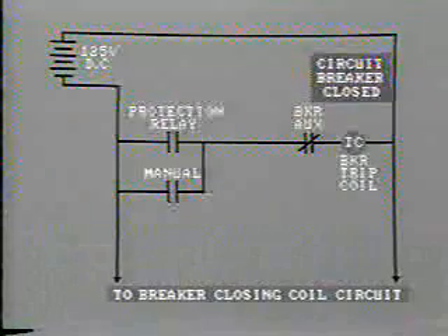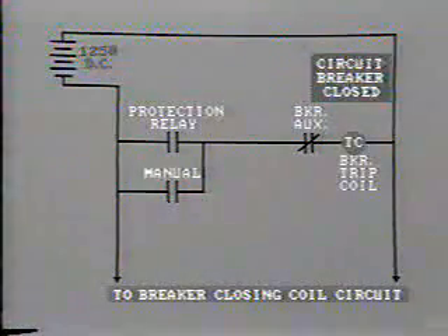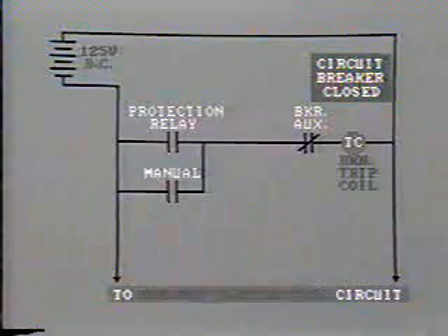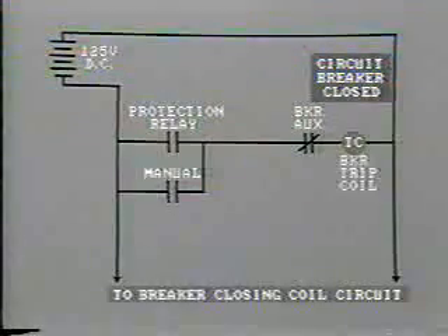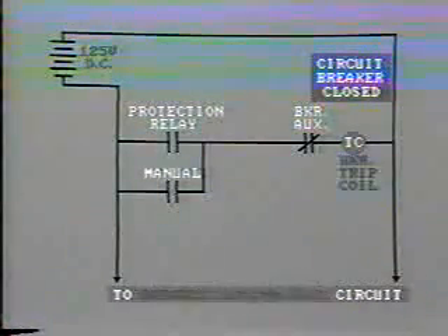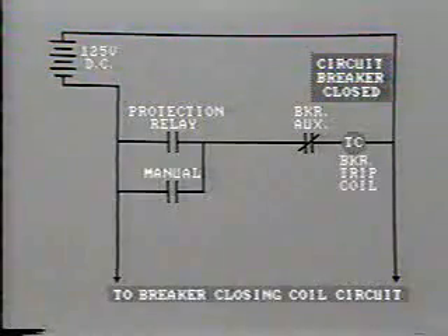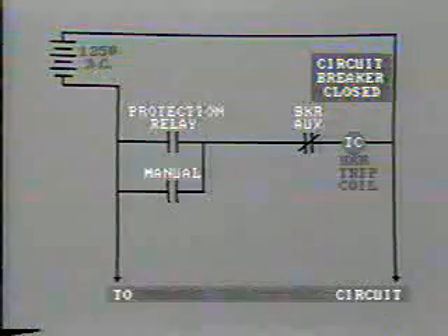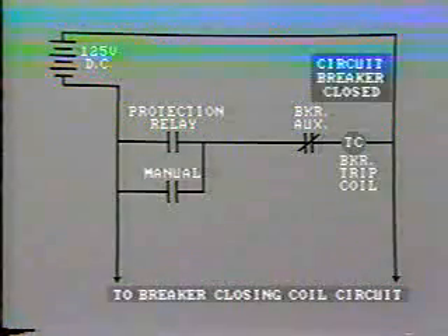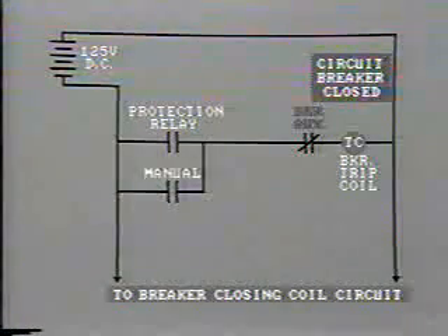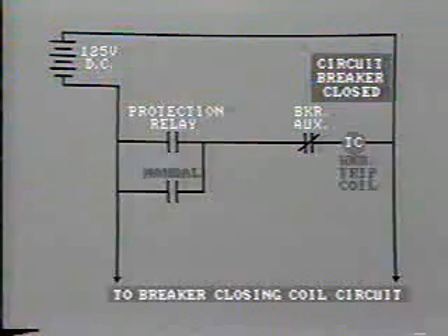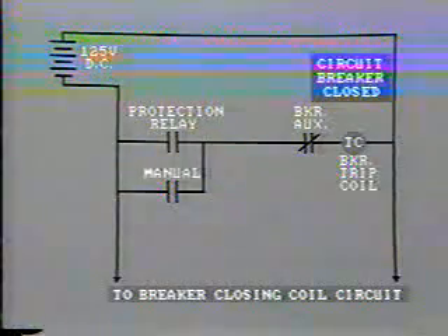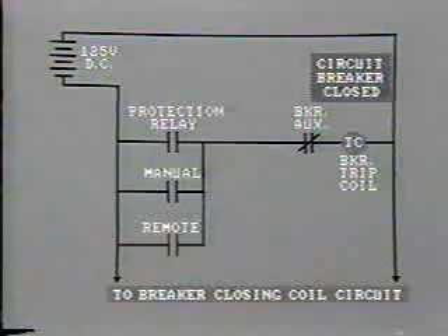Let's look at this tripping circuit. A 125 volt DC system is provided for operation of the breakers. The circuit breaker closing and tripping coils are energized by 125 volt DC from the station battery, as this provides a continuous and reliable power supply. When the circuit breaker is closed, the elementary tripping circuit will look like this. These auxiliary contacts are closed because the breaker is closed, but the tripping coil will not be energized until either one, the protective relay contacts close, or two, the manual switching contacts are operated. In practice, there may be other parallel contacts which can open the breaker.